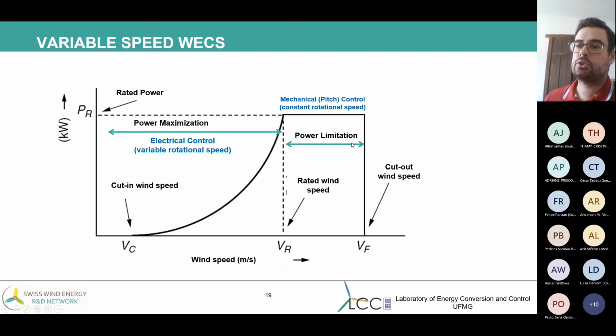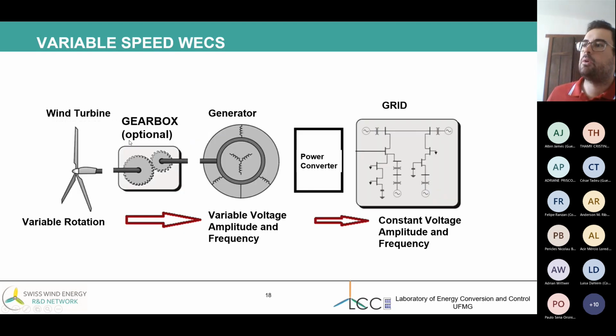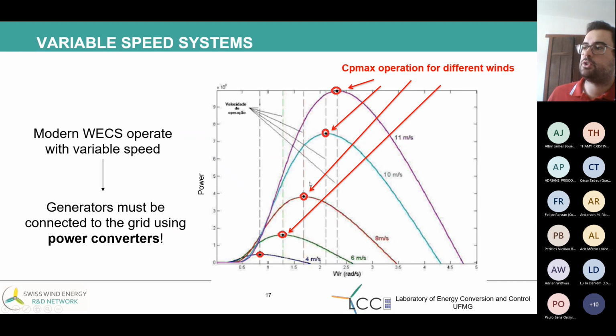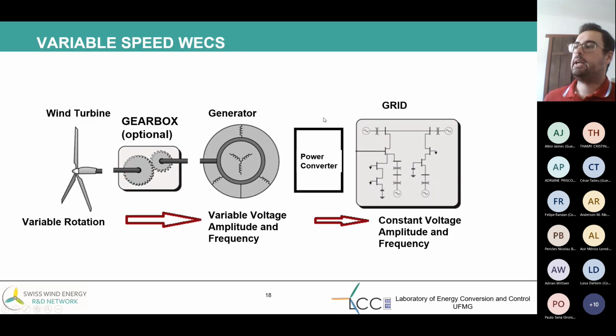And so we come back to the curve of power according to the wind speed. In fact, we explained this curve previously as the power maximization here for the electrical control, but this control is just possible in variable speed systems. The objective is to reach the maximum power point extraction. And for this, it's necessary to use power converters.